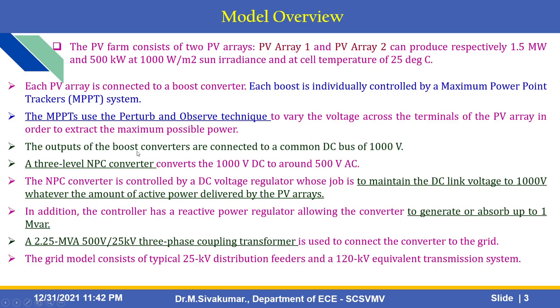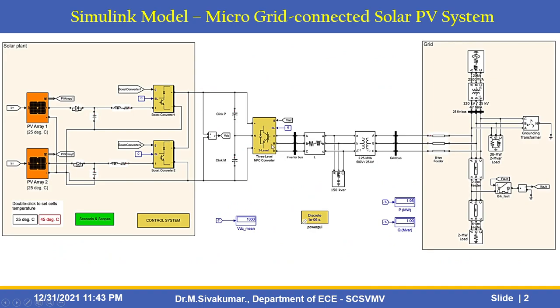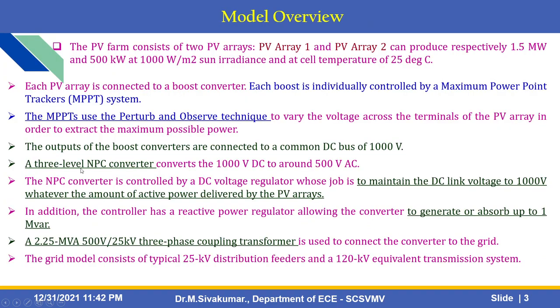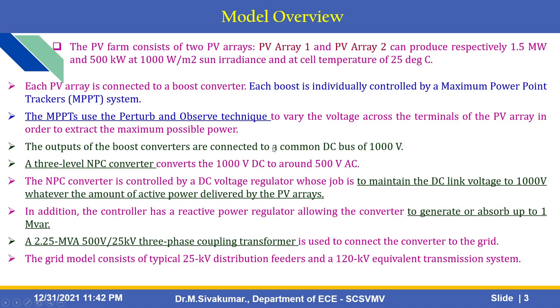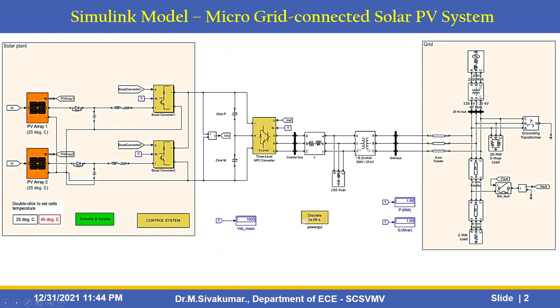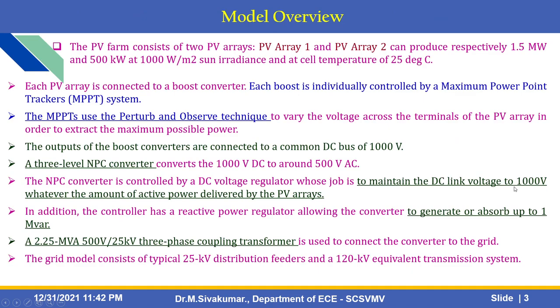MPPT uses the perturb and observe technique to vary the voltage across the terminals of the PV array in order to extract maximum possible power. The output of the boost converter is connected to a common DC bus of 1000 V. A 3-level NPC converter converts 1000 V DC to around 500 V AC. The NPC converter is controlled by a DC voltage regulator whose job is to maintain the DC link voltage at 1000 V regardless of the active power delivered by the PV arrays. In addition, the controller has a reactive power regulator allowing the converter to generate or absorb up to 1 MVAR.